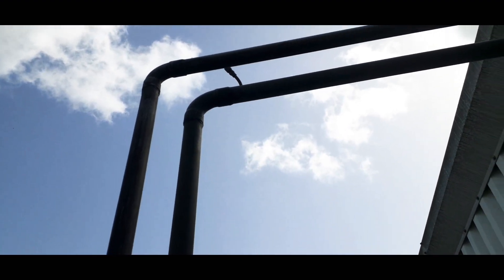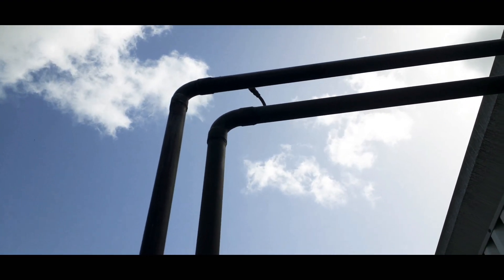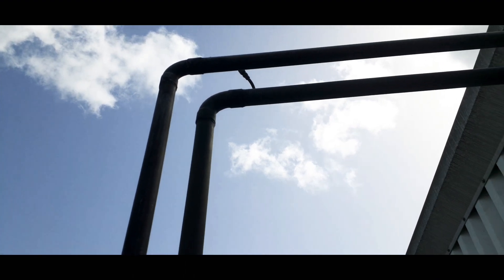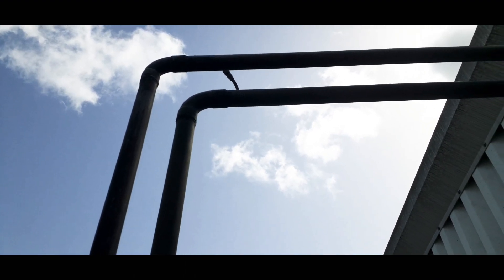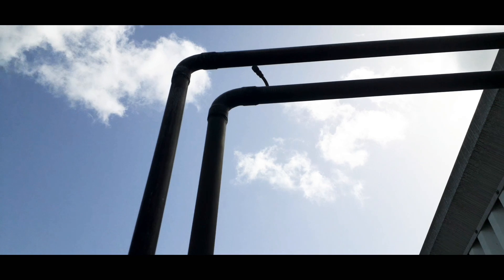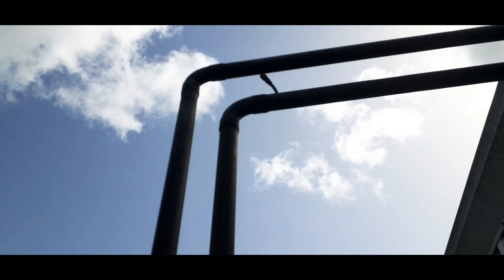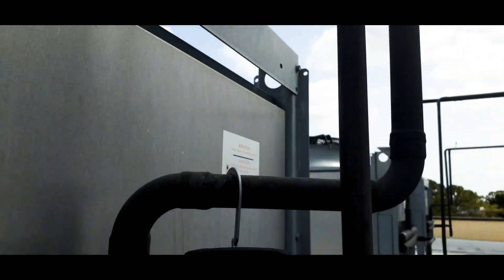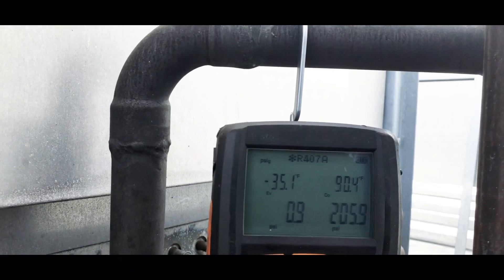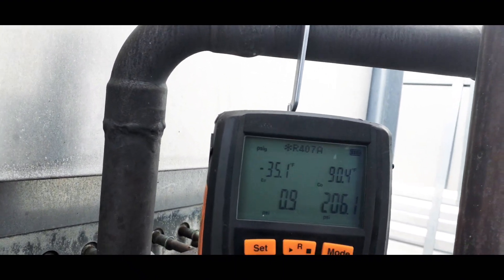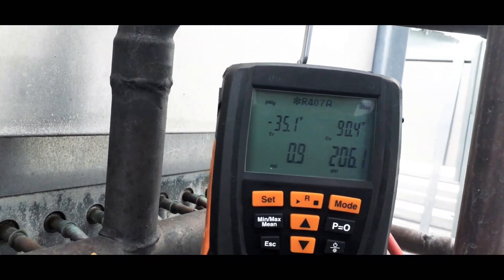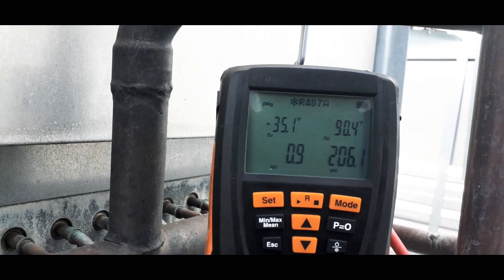Normally if there's air, it's going to be at the highest point. You can get a recovery tank, recover some gas and see how it goes. But as you see, 205 PSI at 90 degrees coil temp - they're pretty close, 90 and 85 - about five pounds difference. There's a little bit of non-condensables showing in this rack.